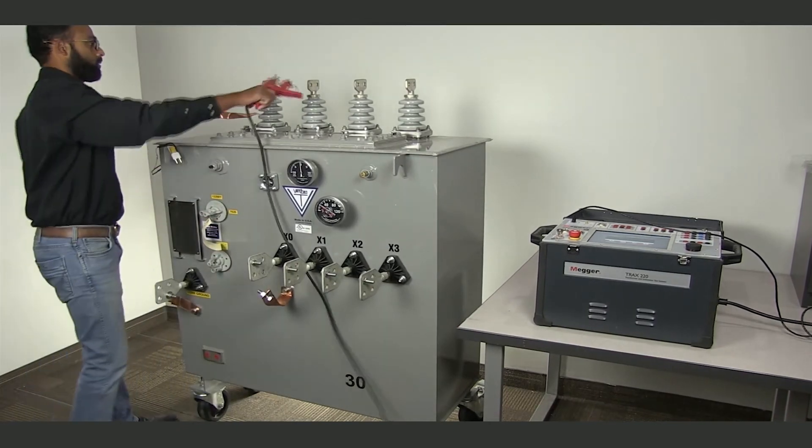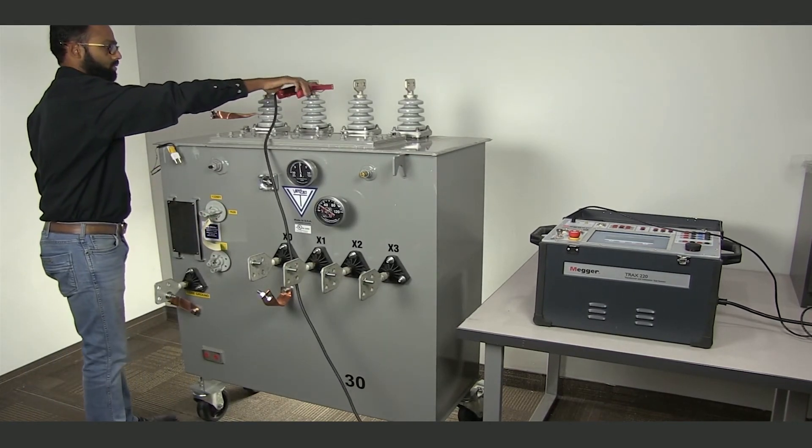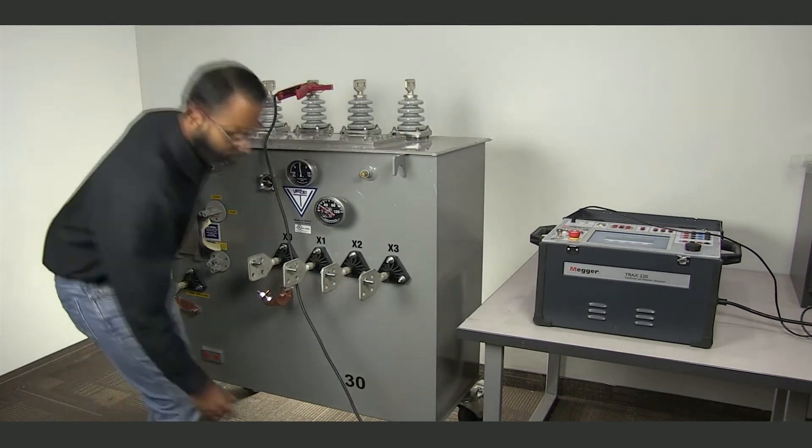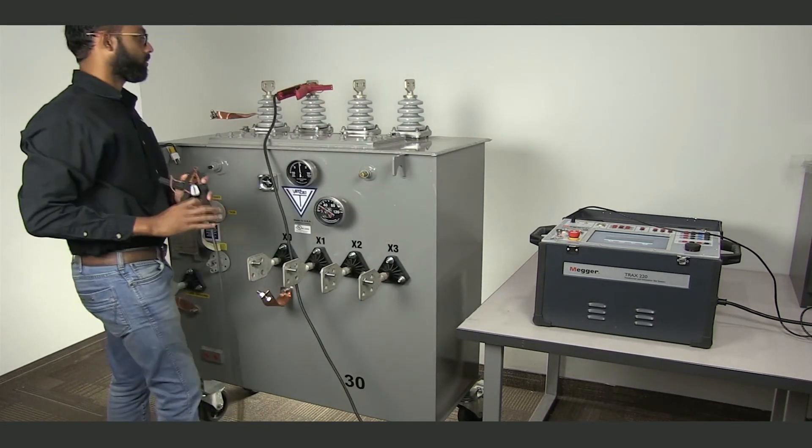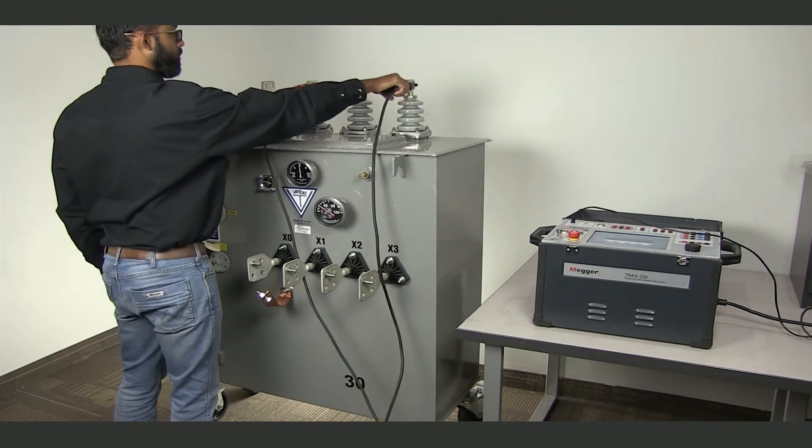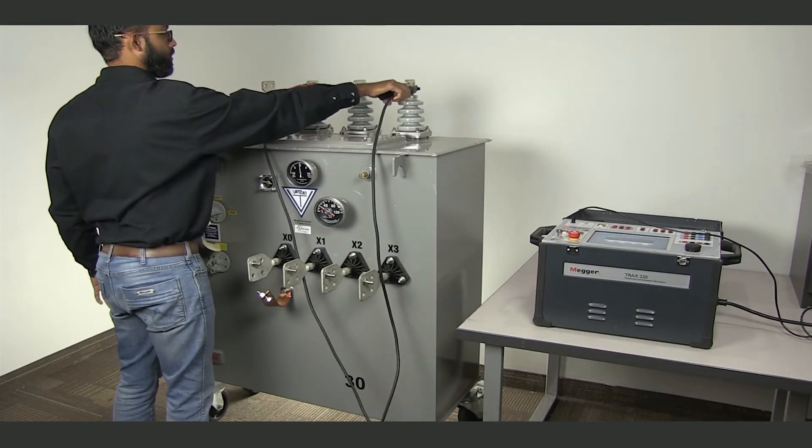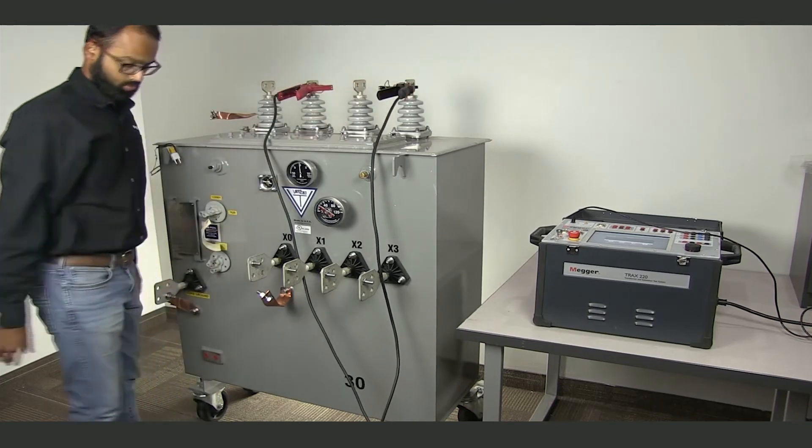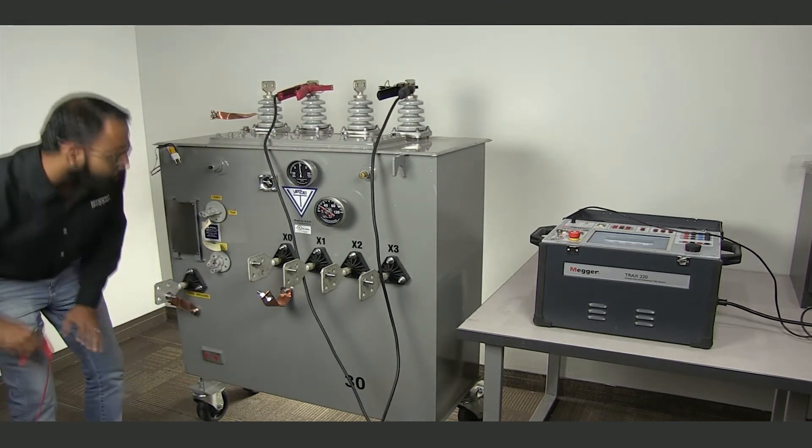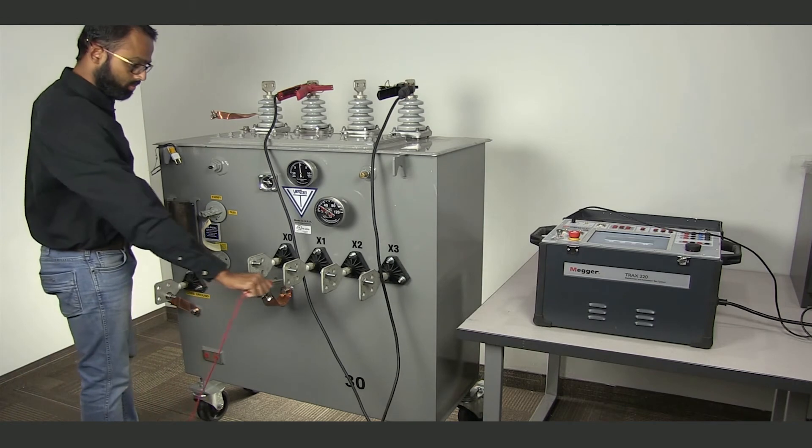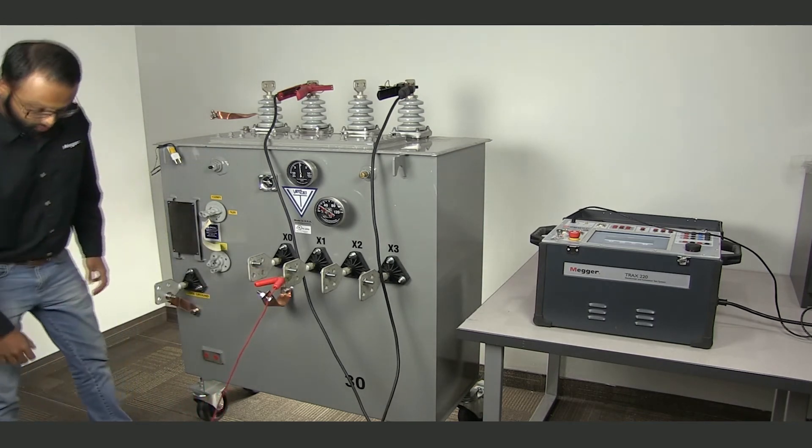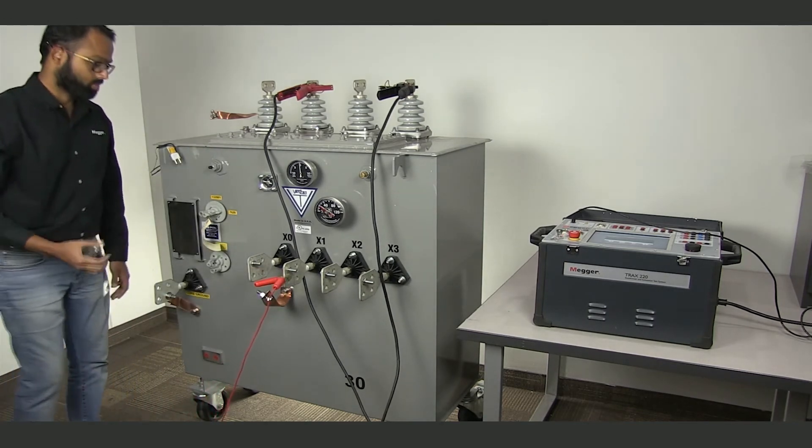I'm going to start off with the A phase. To test on the A phase, I'm going to take the Kelvin cables and connect them on the H1 and H3 bushings. The red one goes on H1 and the black one goes on H3. Polarity is important for turns ratio testing, so make the connections correctly. The sense cables go on X1 and X0 bushings respectively.